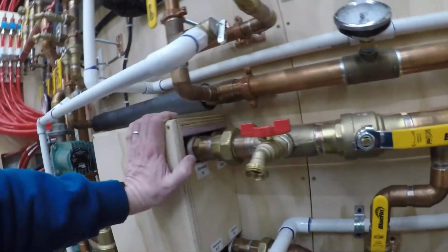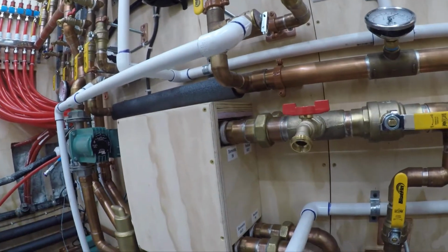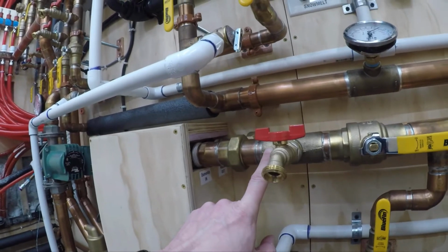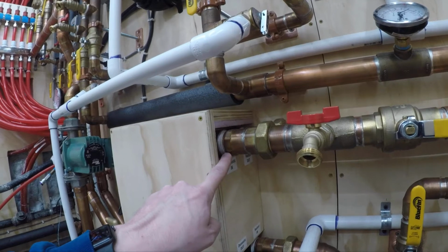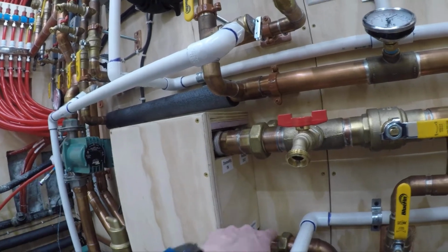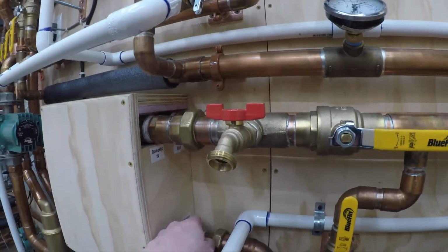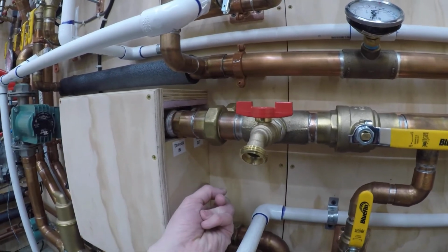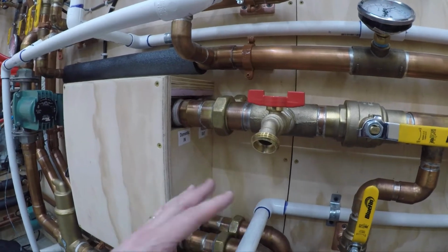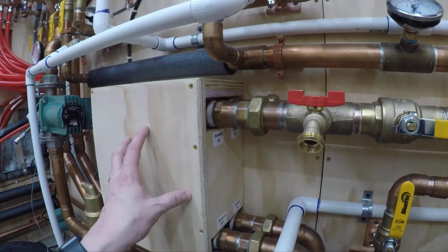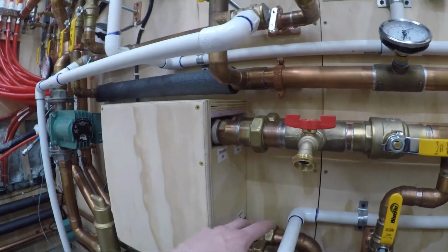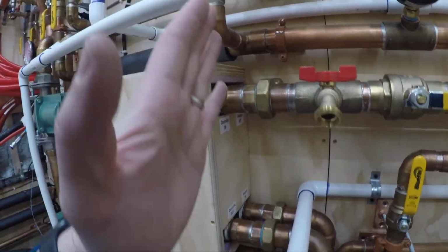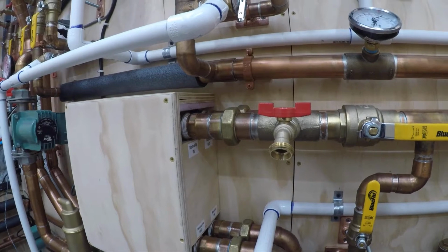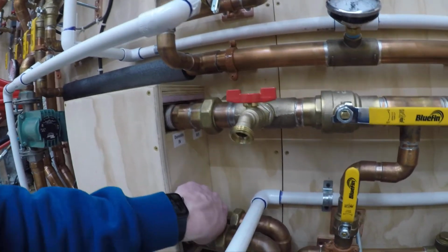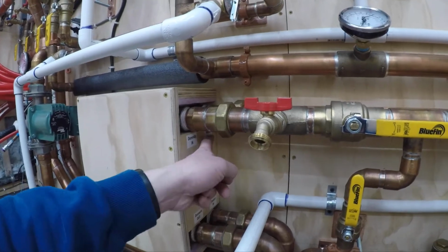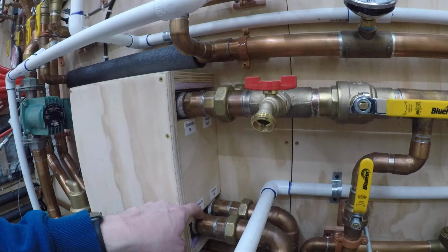So another note for the flat plate heat exchanger, you want these flowing in opposite directions. What I mean is, if you've got your heat from the hot water heaters on the domestic side coming in here at 140 and going out cooler, you want your cold water coming in on the bottom and flowing the opposite direction to pick up the heat as it crosses. As the water flows opposite ways in the flat plate, it's more efficient. It picks up more heat than having them both go in the same side and out. So they're bypassing each other like cars on a highway, versus riding next to each other. This glycol is picking up heat as it goes this way. This domestic is losing heat as it goes this way.